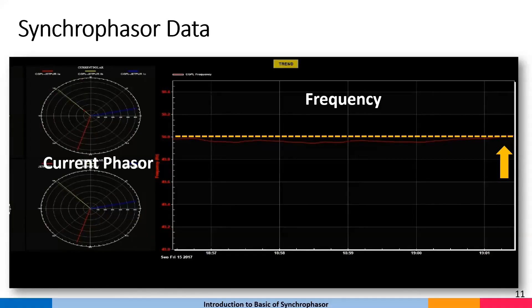So what data do we get from a phasor measurement system? We get voltage and current phasor, and positive sequence components of voltage and current. You can also get negative and zero sequence, but we don't try to get it directly, because if we have voltage and current phasor, we can easily calculate all sequence components from those. We try to get the positive sequence component directly because we don't want to waste calculation time, though it can be done. Then we also get rate of change of frequency.